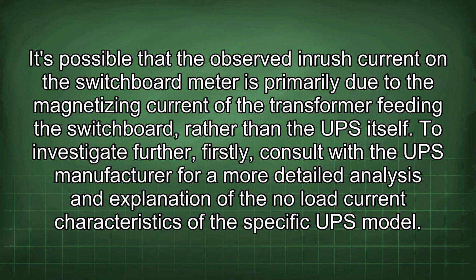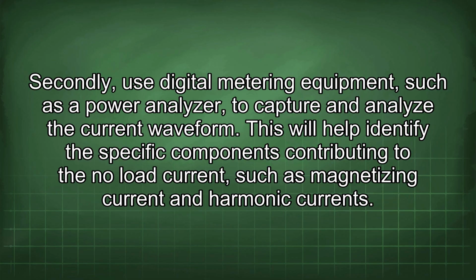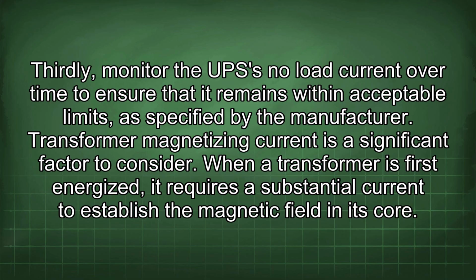To investigate further, firstly consult with the UPS manufacturer for a more detailed analysis and explanation of the no-load current characteristics of the specific UPS model. Secondly, use digital metering equipment, such as a power analyzer, to capture and analyze the current waveform. This will help identify the specific components contributing to the no-load current, such as magnetizing current and harmonic currents. Thirdly, monitor the UPS no-load current over time to ensure that it remains within acceptable limits, as specified by the manufacturer. Transformer magnetizing current is a significant factor to consider.